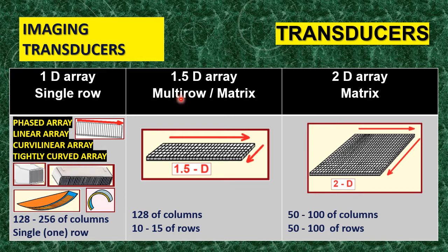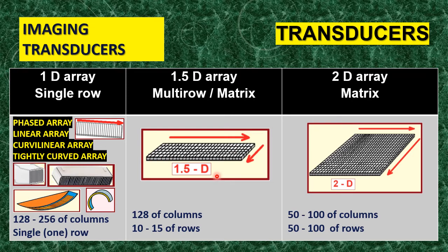The next category is the 1.5D array transducers, sometimes called multi-row transducers. These have multiple rows of columns — typically around 128 or 256 columns — with several rows alongside them. This is in contrast to the single row of the 1D transducers. The multiple rows here are limited in number, for example 7 or 10 rows.